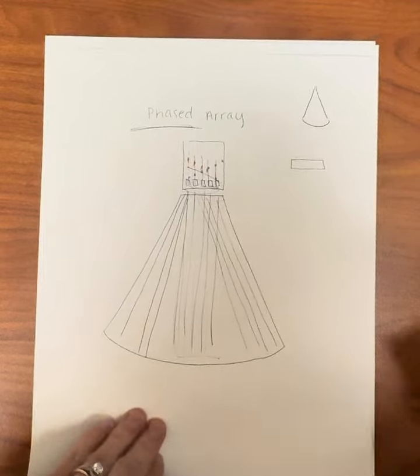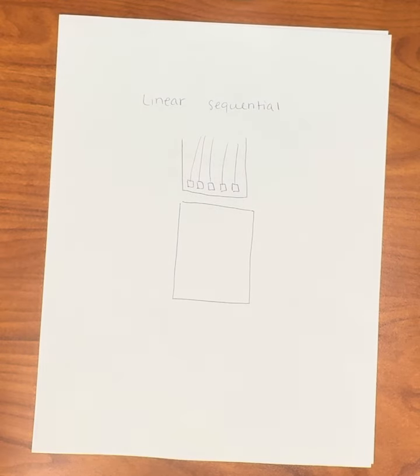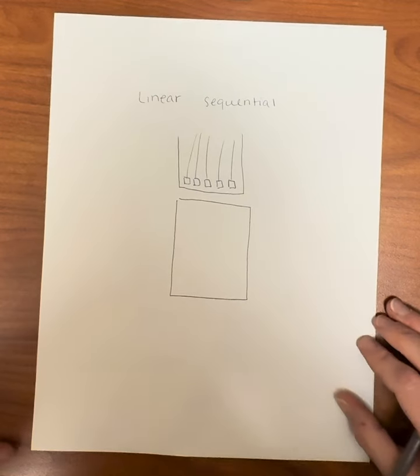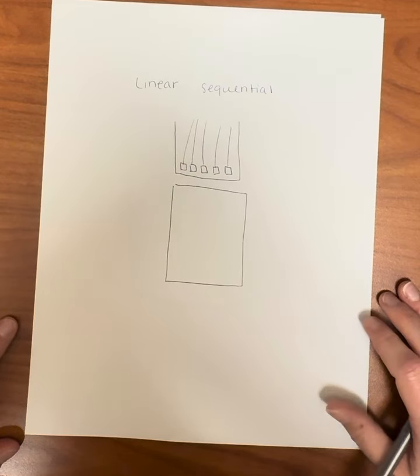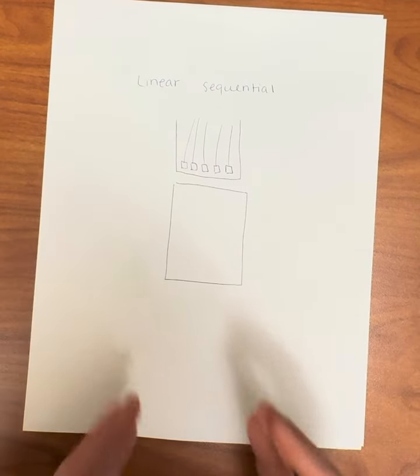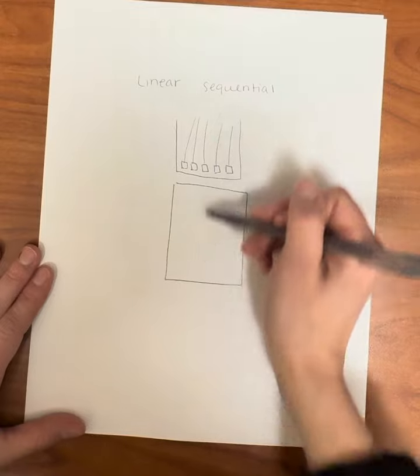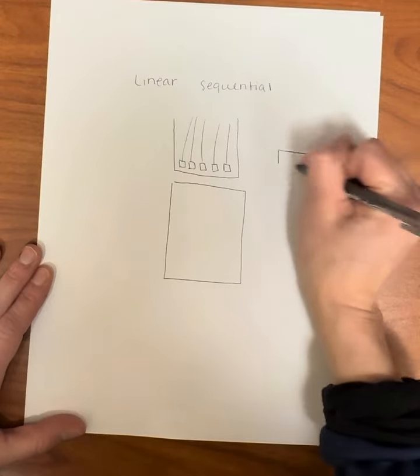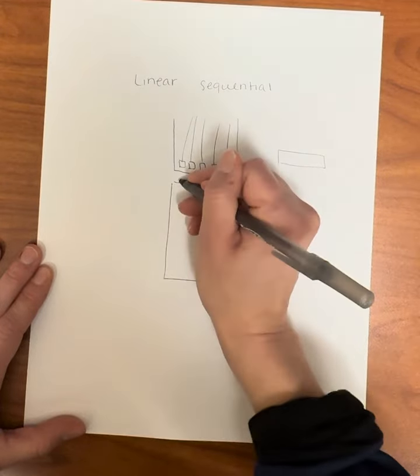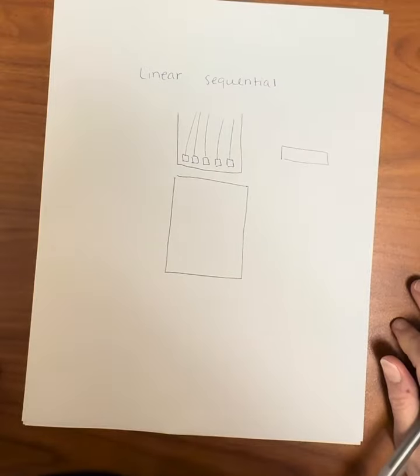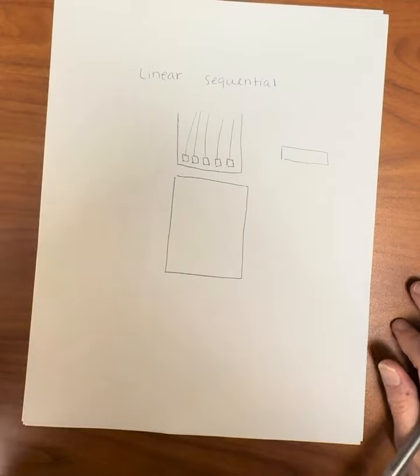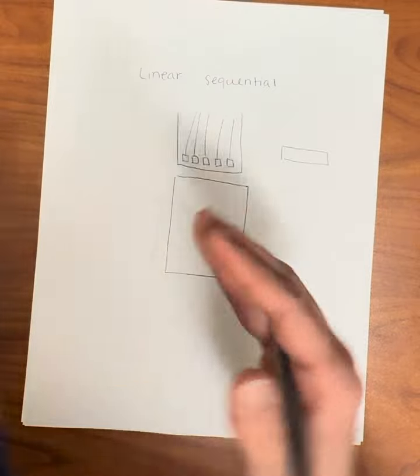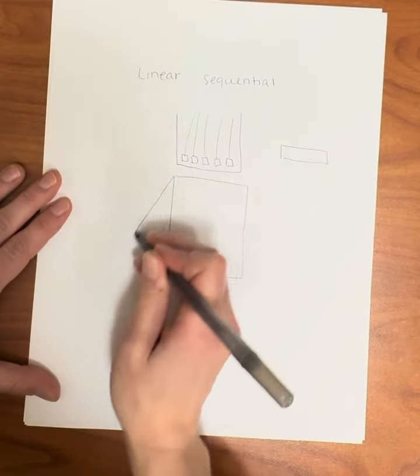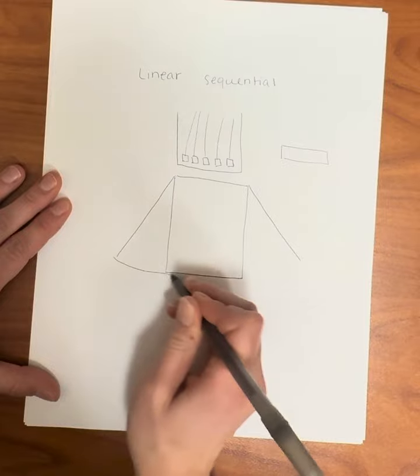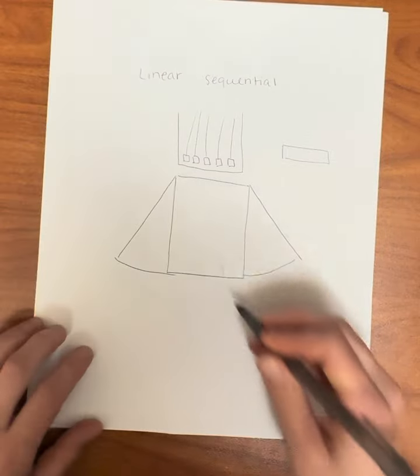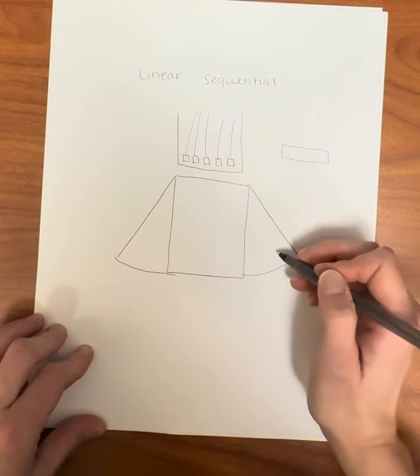Now, traditionally, our linear sequential transducer could not steer, right? Unless it had a motor that was doing it, it would just send sound beams straight down. It has a rectangular footprint, so it makes a rectangular image. Now, typically today, that's how we still use it. But as you saw in lab, right, we can bend that whole image if we want to, or we also can make this into a trapezoidal image. And when we make it into a trapezoidal image, we need that same sort of phasing process.